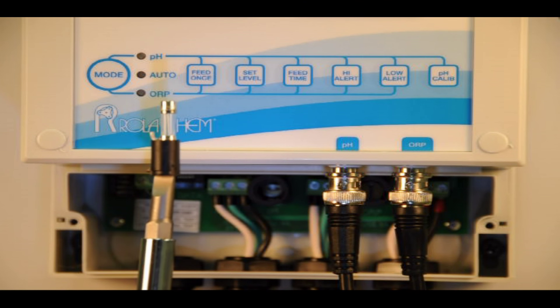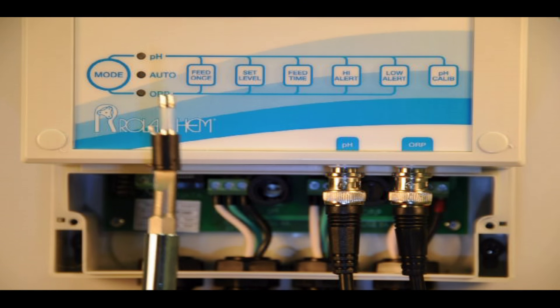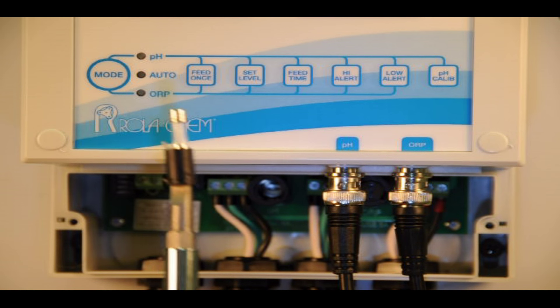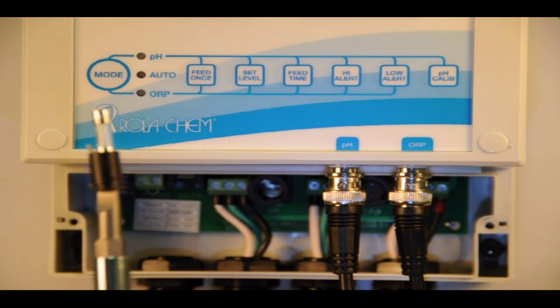One trick you could do is if you had one that was working, say the ORP was working and the pH was not, what you could do is flip-flop the fuses. If the pH works and the ORP doesn't, you probably have a bad fuse.